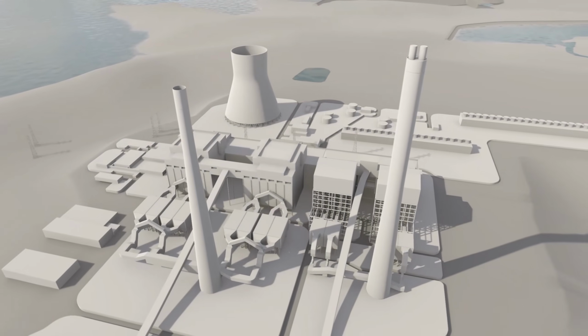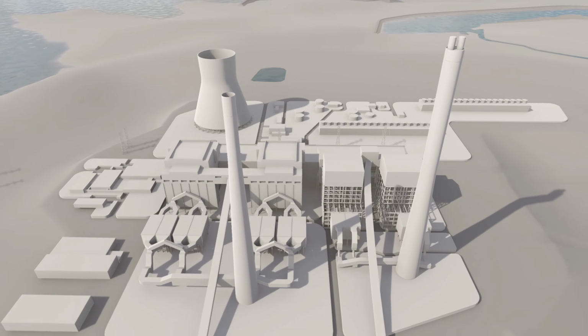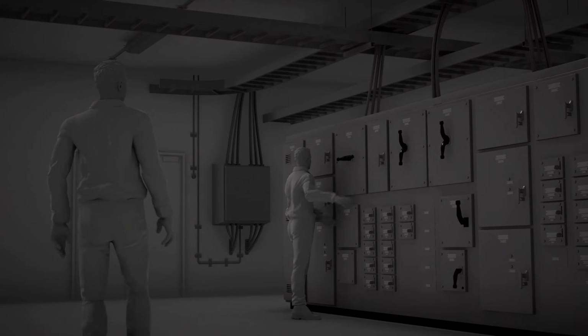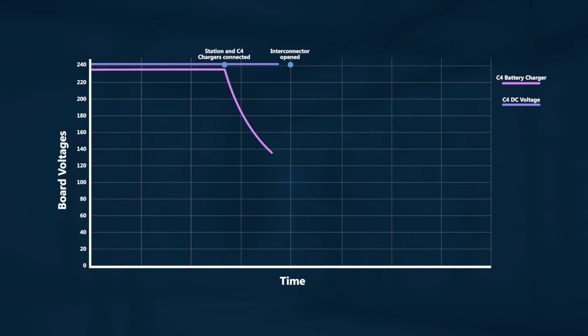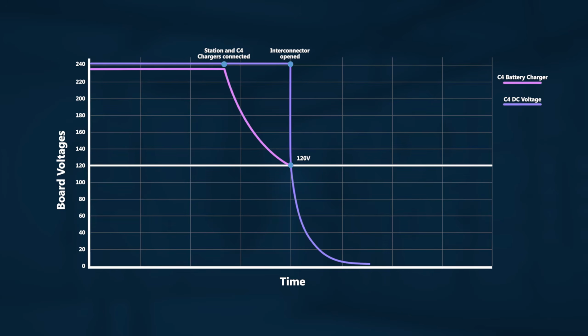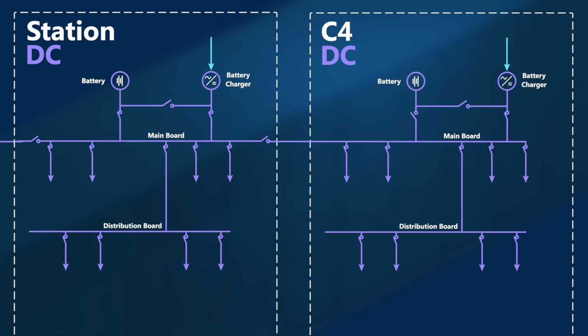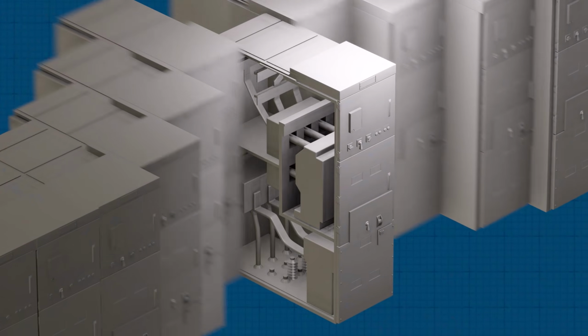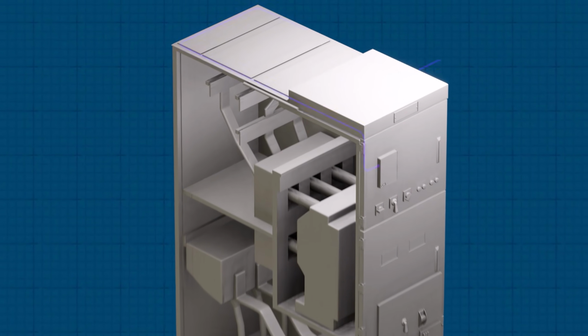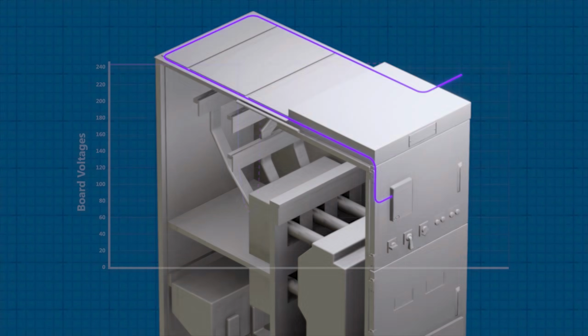A number of factors led to the incident at Unit C4. When the interconnector was opened, the battery charger did not maintain the voltage in the DC system, despite the switching sequence requiring it to do so. Because the battery charger was the sole source of DC power at the time, this led to a voltage collapse in the DC system. And this voltage collapse incorrectly triggered arc flash protection, which tripped the AC system. Then, without AC power, the battery charger did not recover, leading to the complete loss of DC.